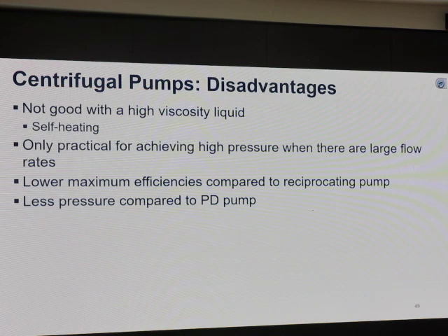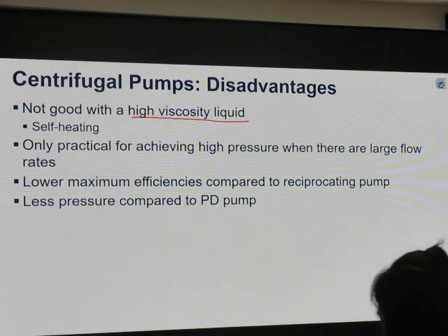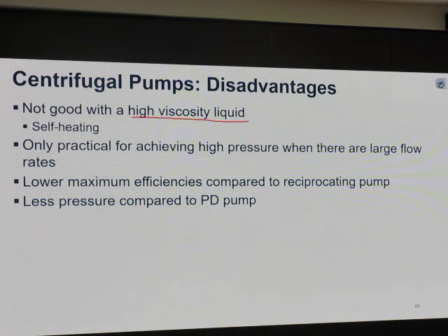Not good for viscous fluid. It can make self-heating. Self-heating means viscous dissipation: the mechanical energy changes into heat when we spin viscous fluid. Typically, if we just pump water, it doesn't do that much, it may do some. But for viscous oil, if we use a centrifugal pump, it generates heat. And it's not good for something that is viscous.